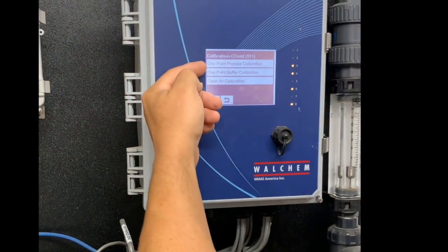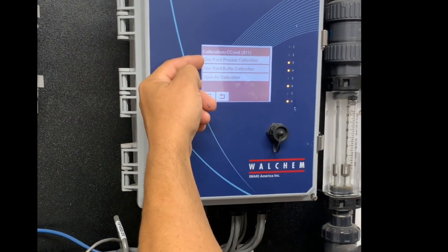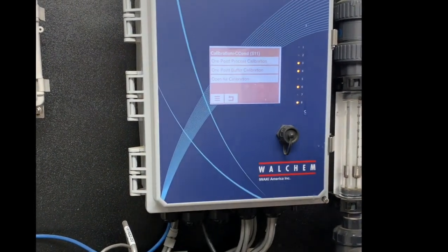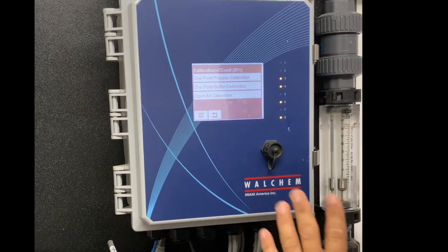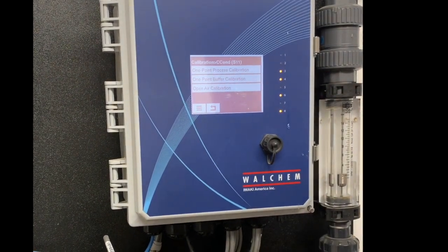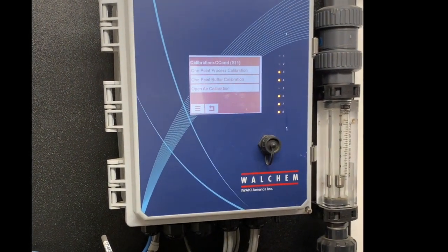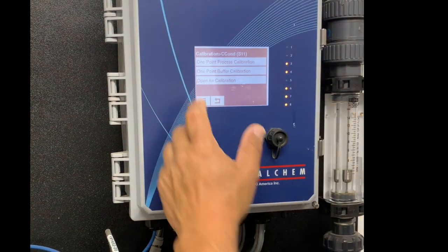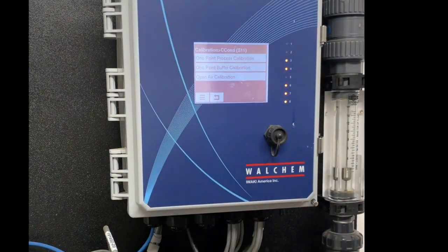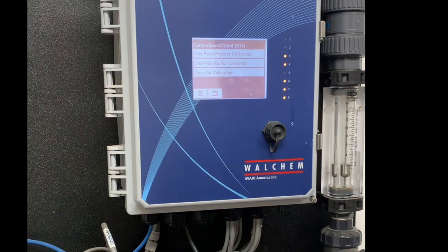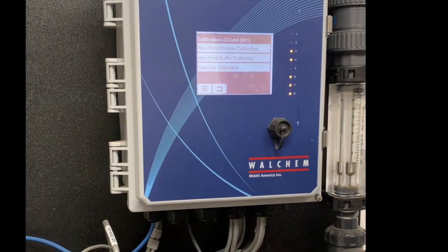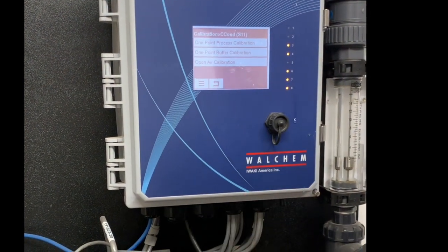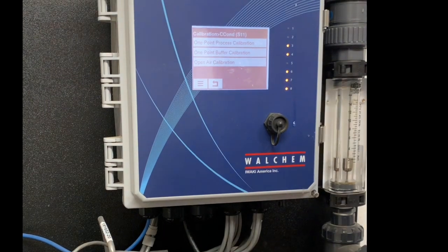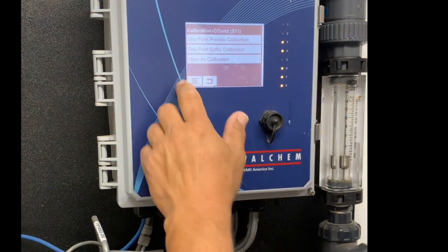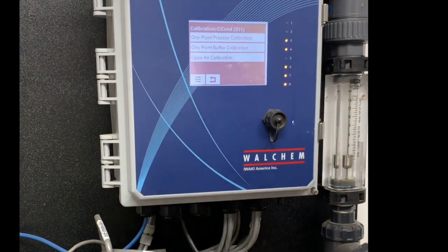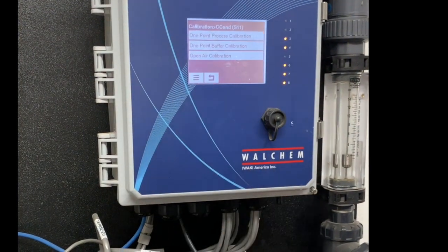So the option that we're going to look at is the 1-point process calibration. That means that you're still running, your probe's in line. It's reading what the actual process is reading. You have a 1-point buffer calibration, or you might have a 2-point buffer calibration for a pH or ORP probe. Those are if you actually have buffers and you pull them out and you'll put them inside of the buffers and do your calibration. Now with the contacting conductivity probe, you have an open air calibration.